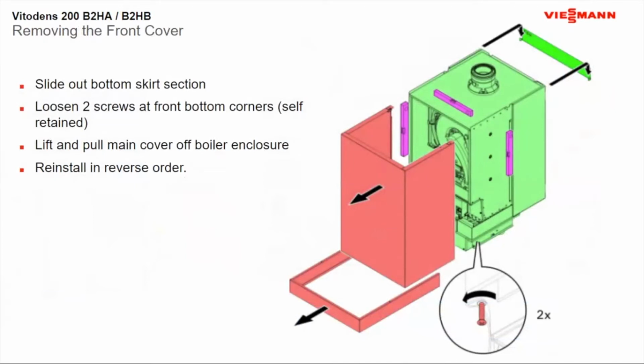So if you've never worked on the boiler, I always like to point out that on the 200 especially, we tend to hide the screws on the cover. So normally to get the cover off the boiler, you have to remove that bottom skirt. It just slides straight out towards you. And then you'll have to look up inside here on the right and left-hand side of the boiler. They're recessed up there. So you have to actually look up inside this piece of plastic, and then you'll see the screws. And then you'll just loosen them up. You'll feel them drop, and then you'll stop. The plastic holds them up in there so you don't lose them. Then you'll be able to lift up the cover and then slide it out towards you.